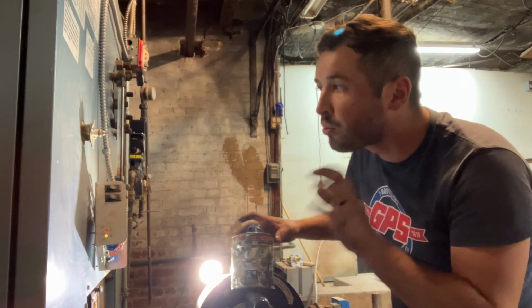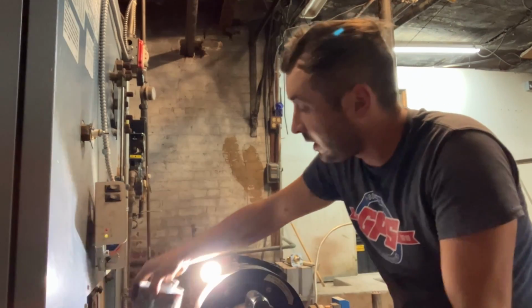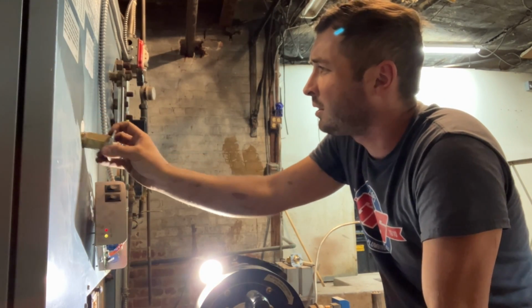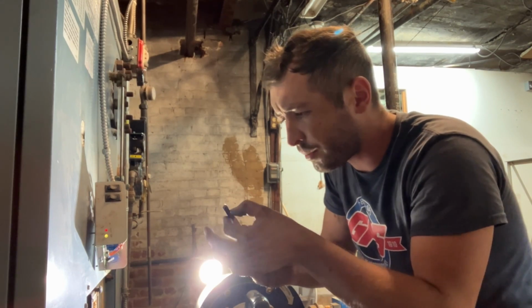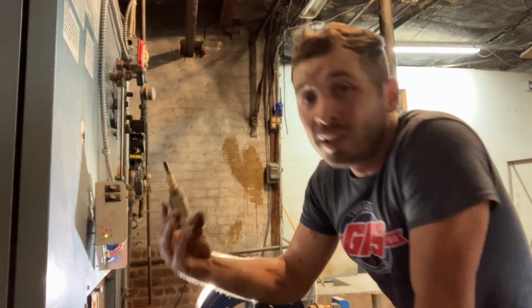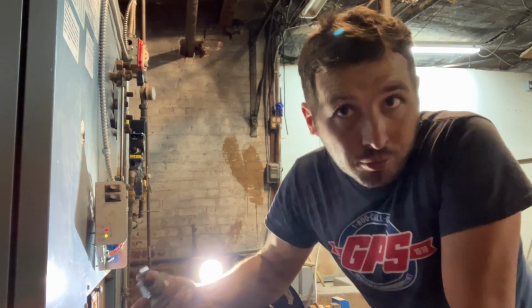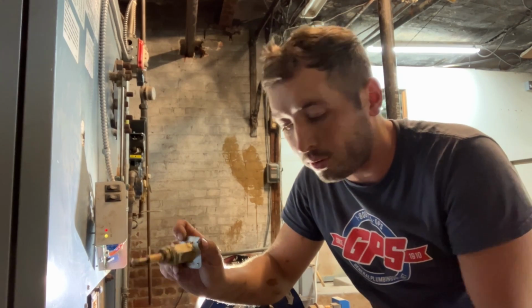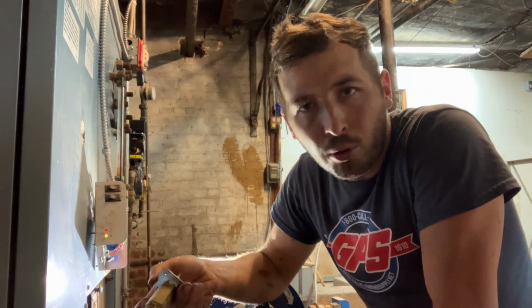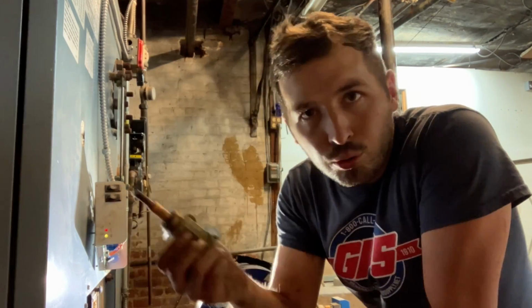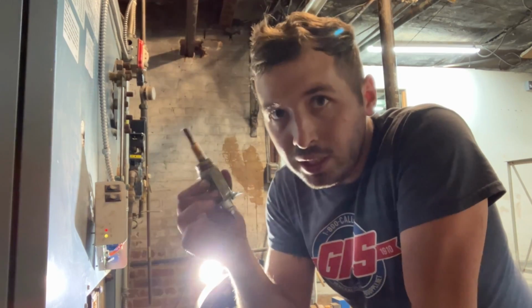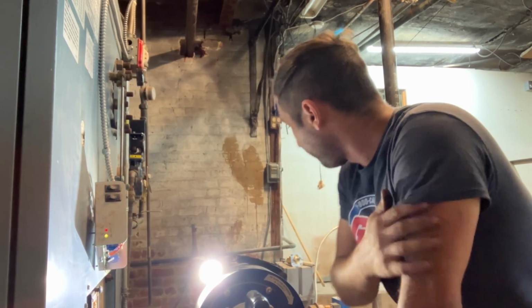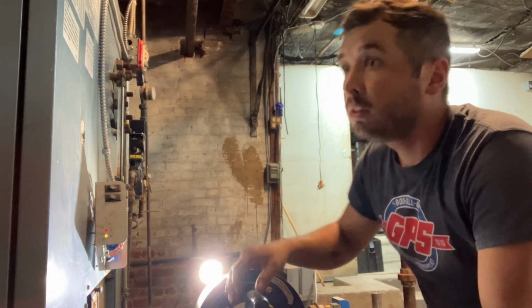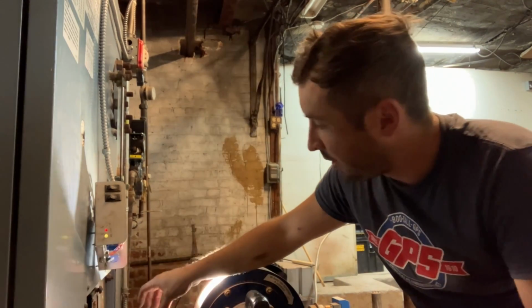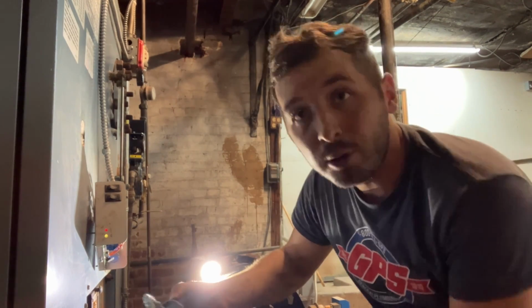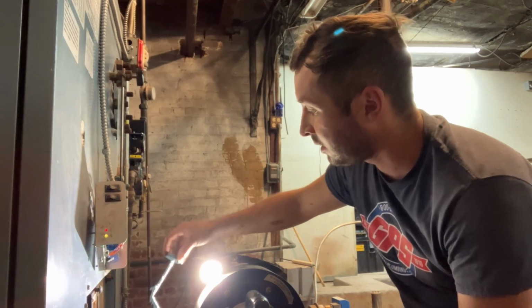How much longer do we really think we're gonna get out of this probe? Based on the age of the boiler and the condition of the probe, I'm pretty sure this is the original probe. Some probes are recommended to be changed every 5 years, regardless of condition. That doesn't mean the older probes aren't good, but is the juice worth the squeeze? Do we really think we can get more time out of this low water cutoff probe, being that it's potentially 8 years old? Or should we just go ahead and swap it out so we don't have to worry about it? It's one less thing.